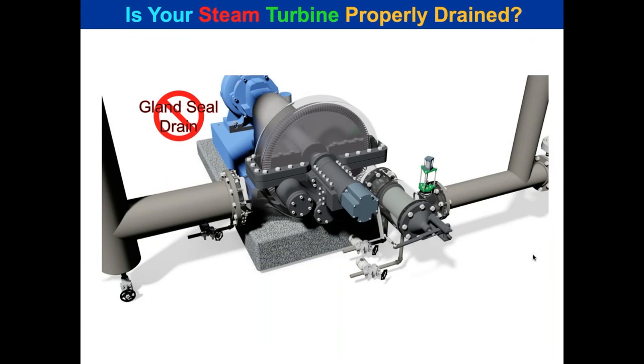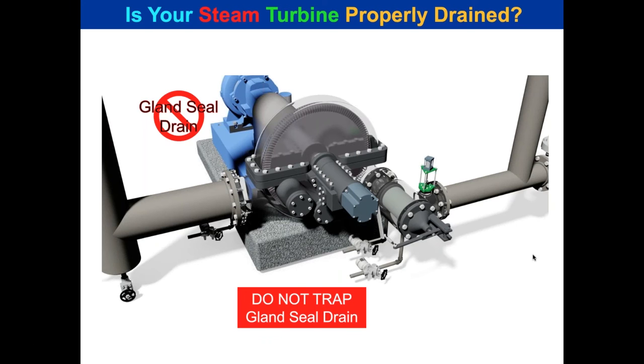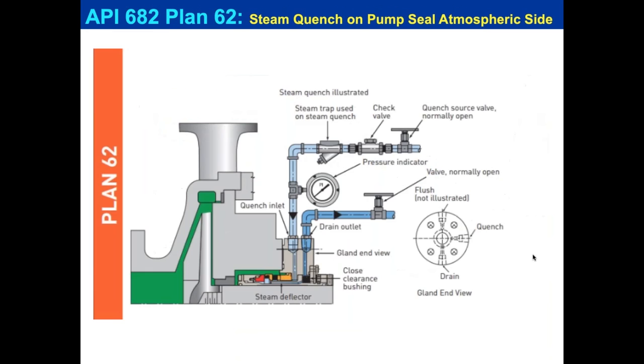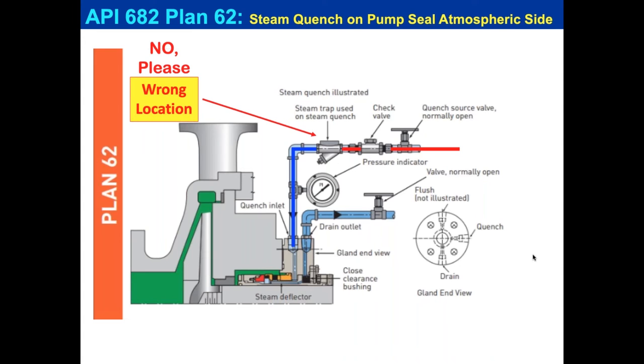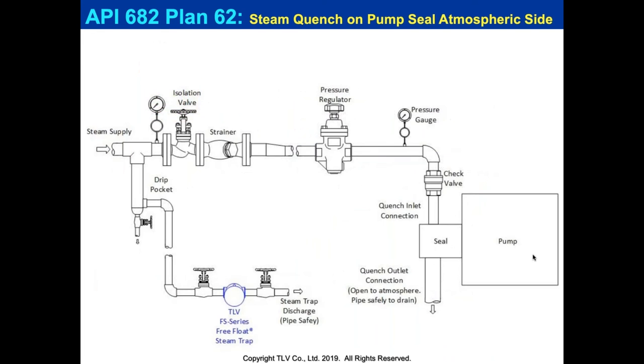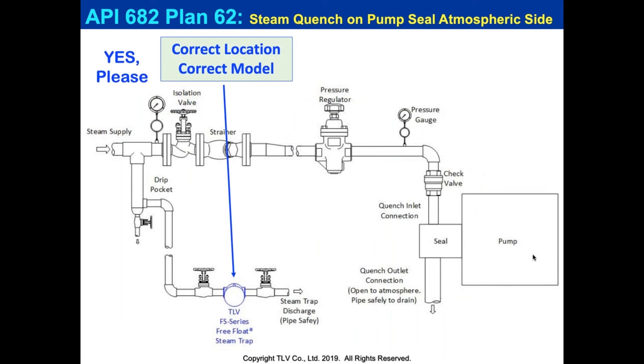Before leaving turbines — what about gland seal steam drains? Don't trap the gland seal steam drain incorrectly. Per API 682, one vendor drawing actually shows it incorrectly — condensate discharging right into the seal. What you want to do is trap it prior to the pressure regulator, so steam has an open outlet safely piped to drain. Get rid of the moisture before it goes through your pressure regulator.